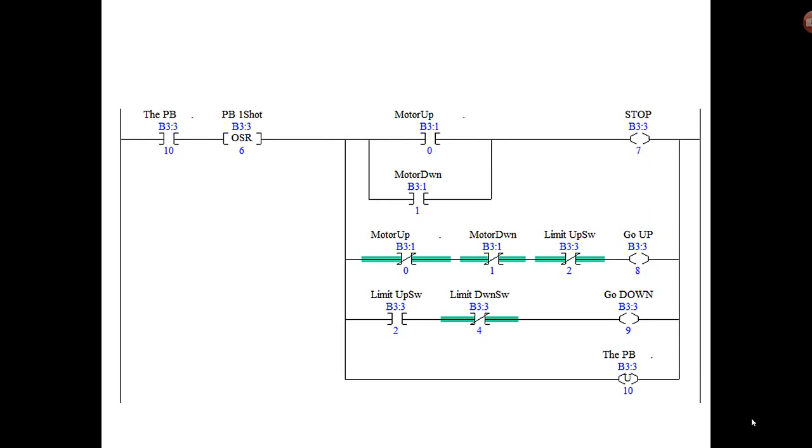So the first branch there sets the stop bit, the second branch sets the go up bit, and then the third branch: if the limit switch in the up direction, or the door is at the top of its travel and it's tripped that switch B3:3/2, then that would be true and we would want the door to go down when we hit the button. Now I threw in the down limit switch as well. In other words, the up limit switch is on, which means the door is all the way up, and I added the down switch as a safety, as a preventive.